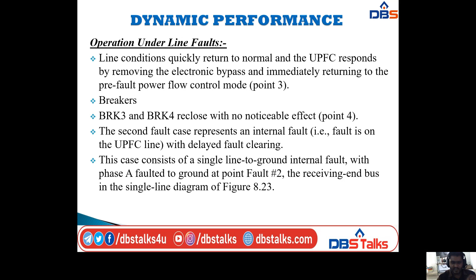As before, at the onset, the UPFC is operating in automatic power flow control mode with P equal to 1 per unit and Q equal to 0.02 per unit. Fault clearing by opening breakers, that is breaker 1 and breaker 2, is delayed until 12 cycles after fault initiation. Previously we had 9 cycles after fault initiation, but here it will take 12 cycles.